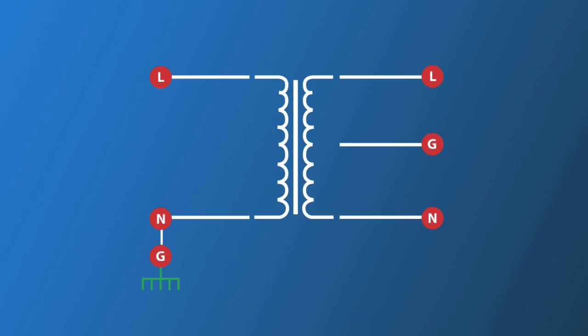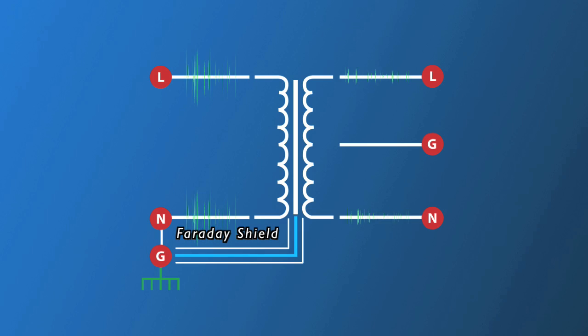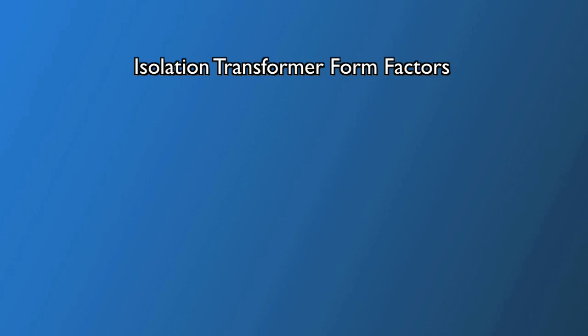Though there are many types of isolation transformers, they are not equal. An isolation transformer that is not symmetrically balanced will reduce a great deal of common mode noise as long as it's been created with proper ground strapping and an effective Faraday shield to minimize capacitive coupling. However, without precise balancing, the noise reduction is typically not as great nor as linear, which is critical for maximizing system performance. There are many form factors, or shapes, for isolation transformers.